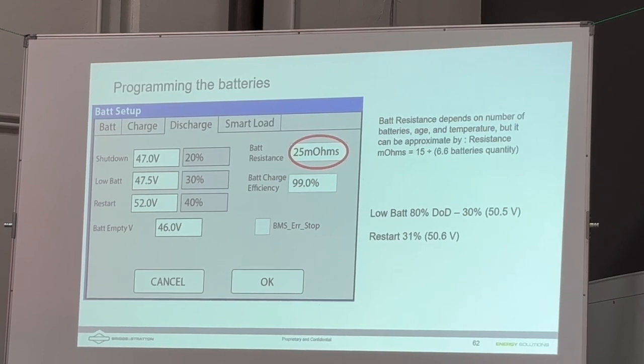The restart value here is, actually I got this wrong before. So the restart value that is there is the value at which it will start redischarging your batteries if grid is also present. So if you have grid present, you would like the grid to power all the loads until your batteries get above that value. If you're below 40%, let's suppose you're at 35% and grid goes off, it will discharge your batteries. Okay, so that value, the restart is only for when grid is present. It will use grid to power the loads until you get above that 40%.